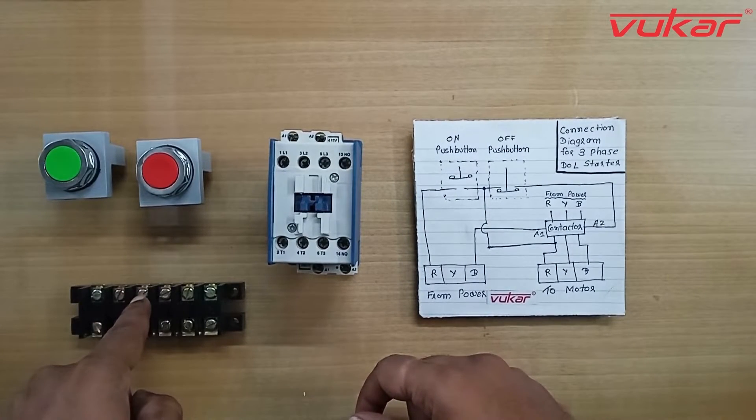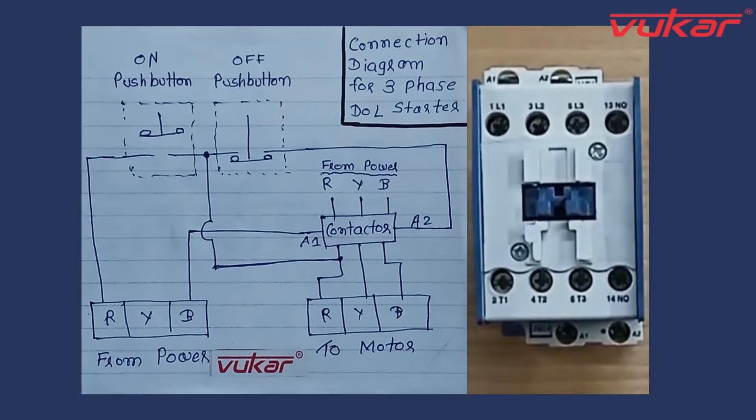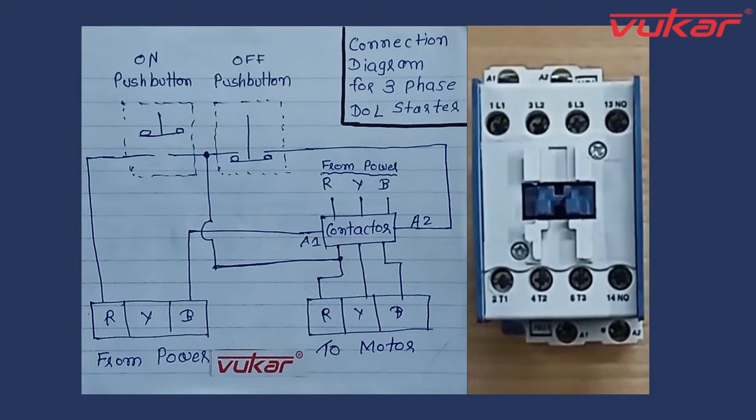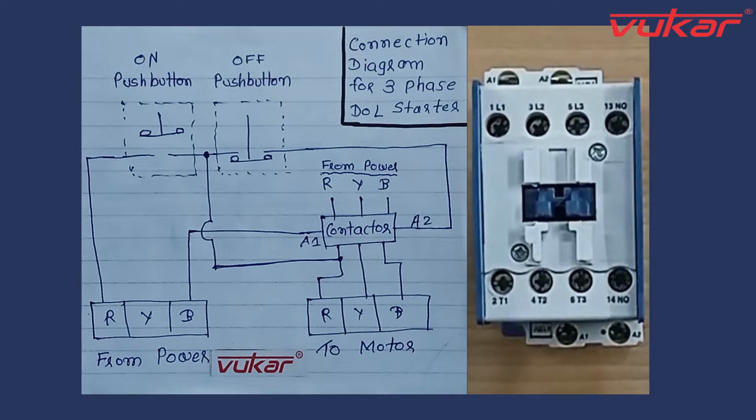Here you can see that the contactor coil A1 is directly connected with B phase. From the contactor, you can see that input terminals L1, L2 and L3 are directly connected with R, Y, B power source.